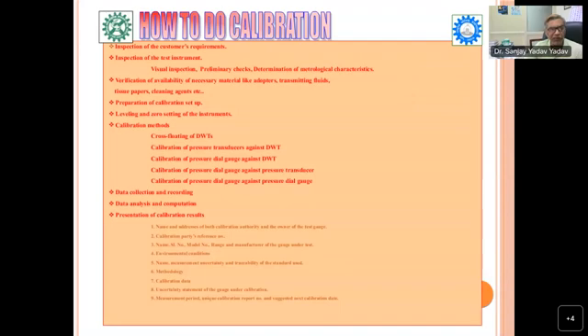Then another was how to do calibration. So how to do calibration? You need to have inspection of the customer requirement, and this particular slide will also help you to make your calibration procedure. If you make your requirement on these points, you can easily make your calibration procedure. So the foremost thing is you have to verify the customer requirement when the instrument comes.